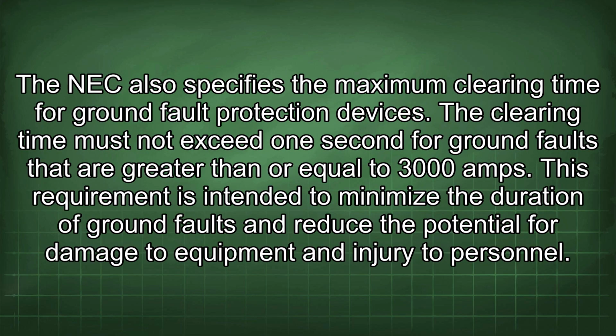The NEC also specifies the maximum clearing time for ground fault protection devices. The clearing time must not exceed 1 second for ground faults that are greater than or equal to 3000 amps.